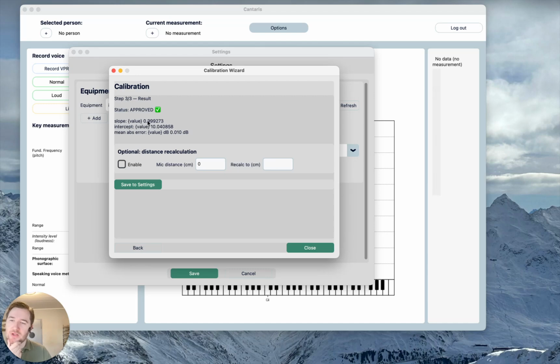When Cantaris wants to calculate its own value to be the one that the true decibel meter would have set, it would say 0.999 times my own measurement plus 10. And that is exactly right, because for the sake of this trial, I added 10 decibels to every measurement. So Cantaris found out that if it takes its own measurement and adds 10, then it'll be exactly like this meter said.